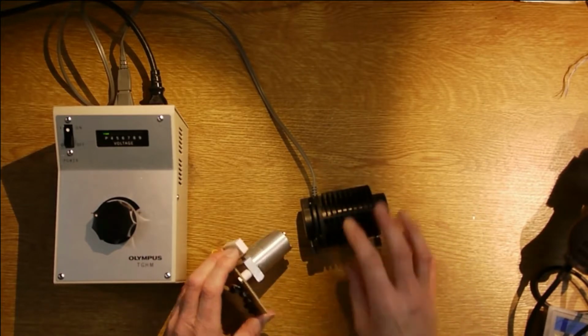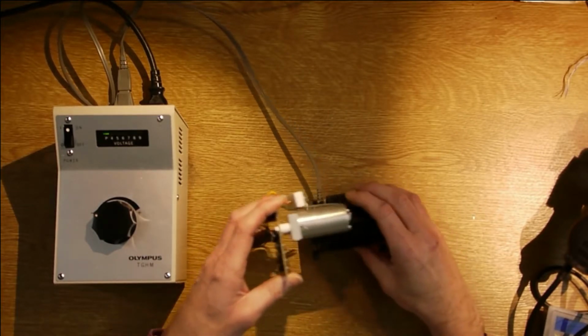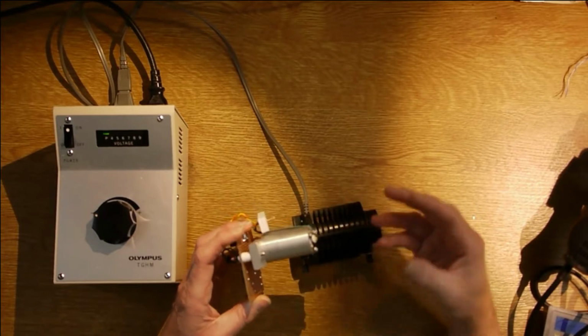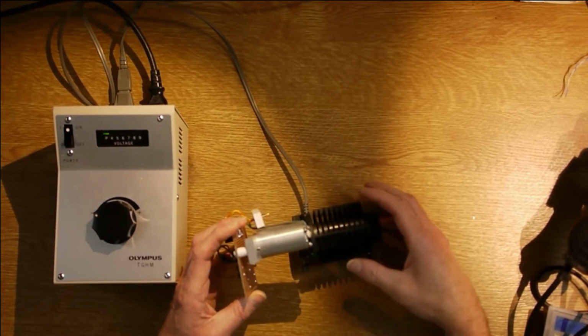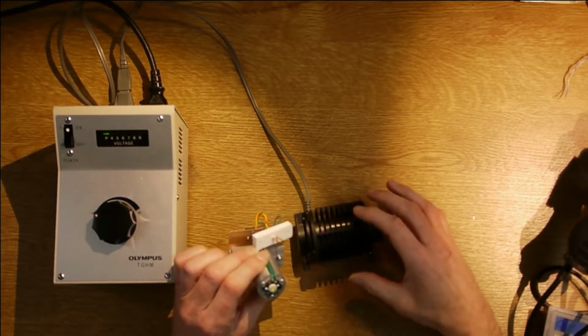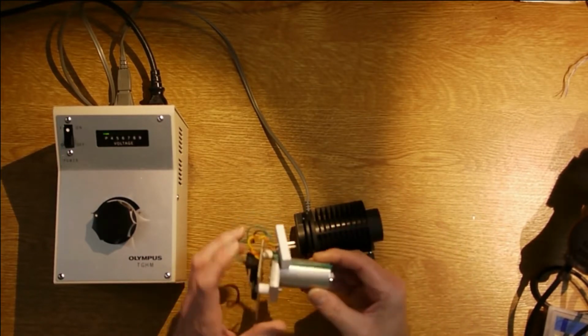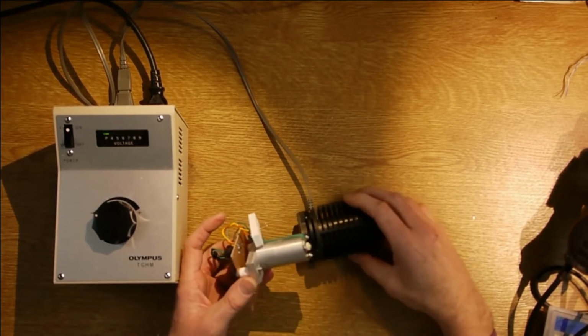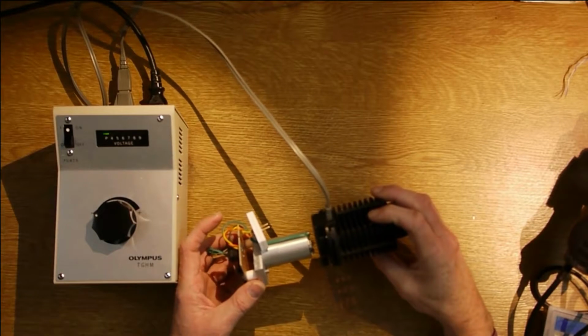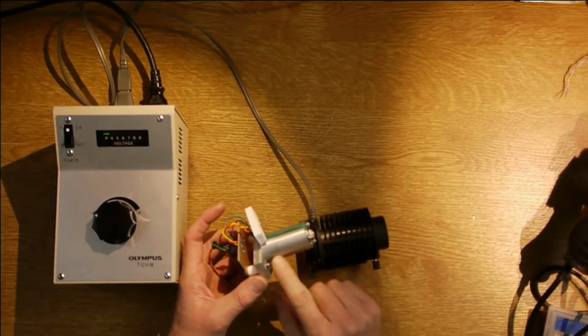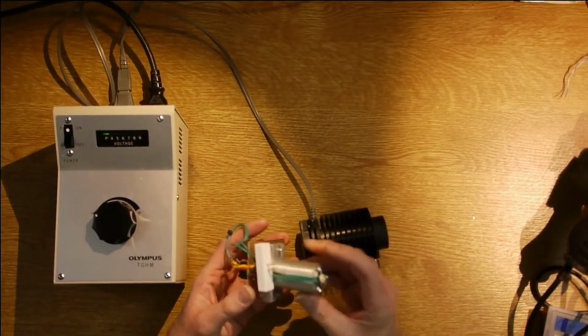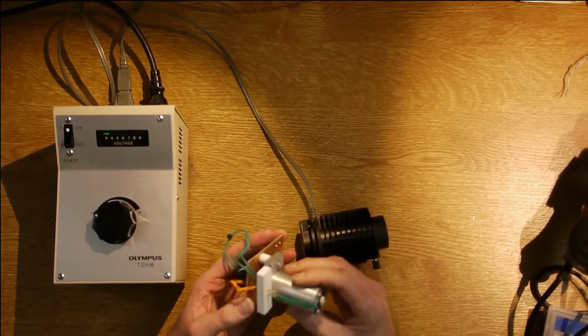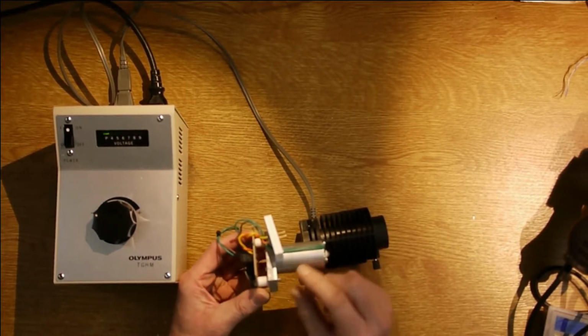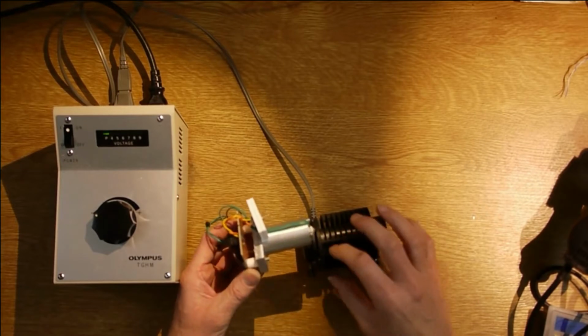Now, if you don't do that, you move this in or out this way, you end up with a bright spot in the middle of the field of view of the microscope. So this does work quite well. It is brighter as well than the bulb. So this is also a heatsink here, because this LED does get a little bit warm. It doesn't get hot, and this does dump the heat out the back of the assembly.